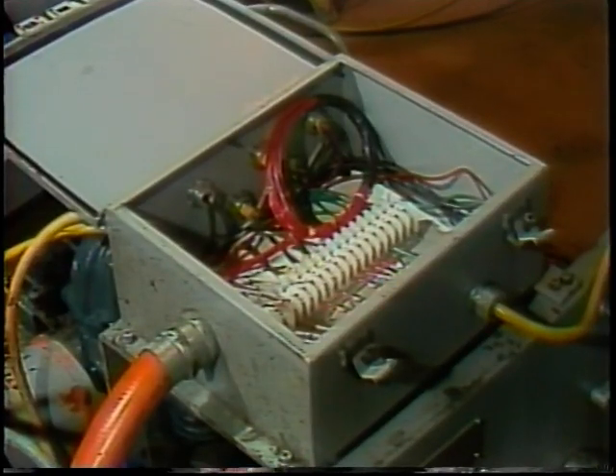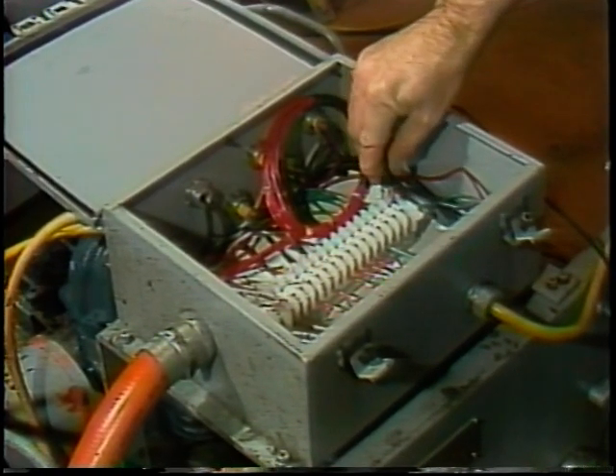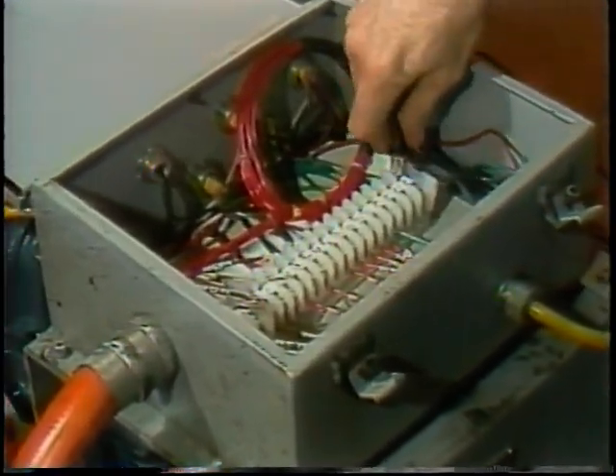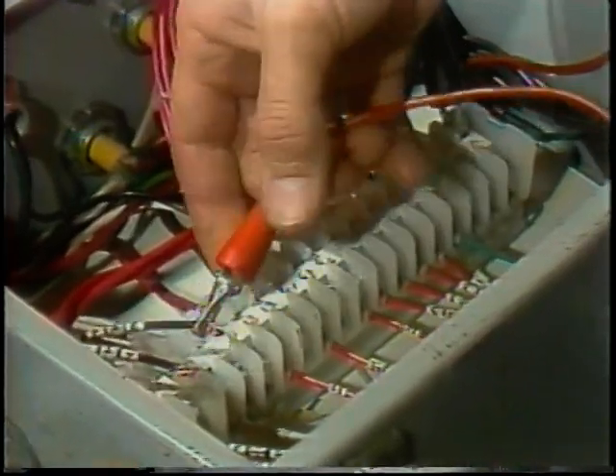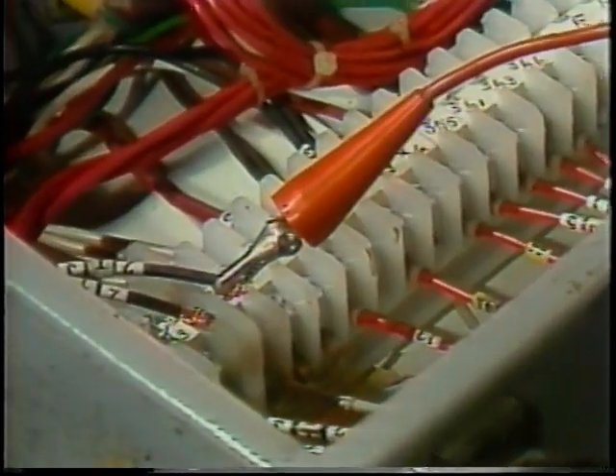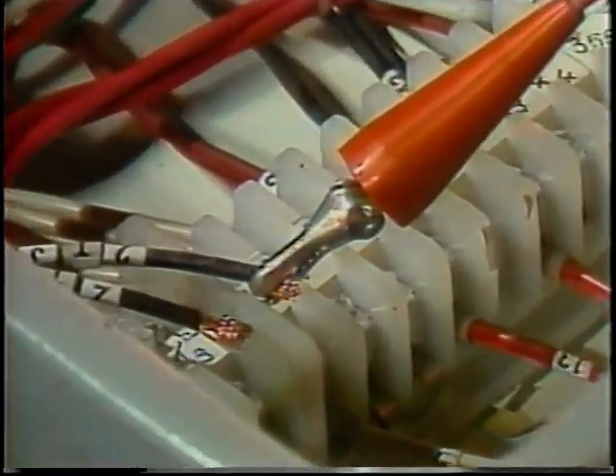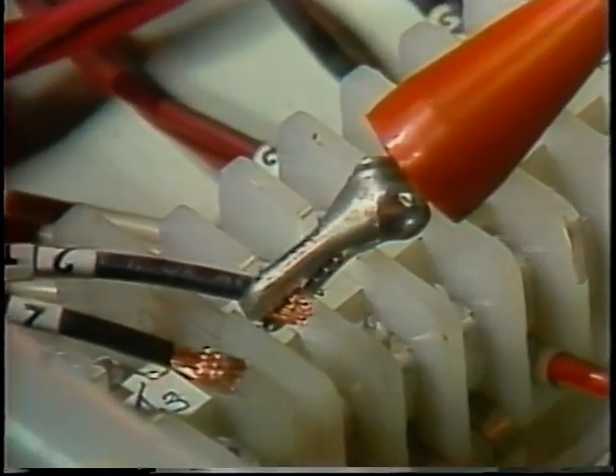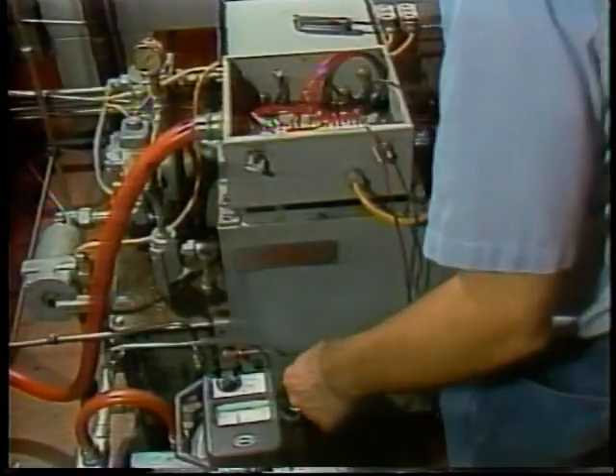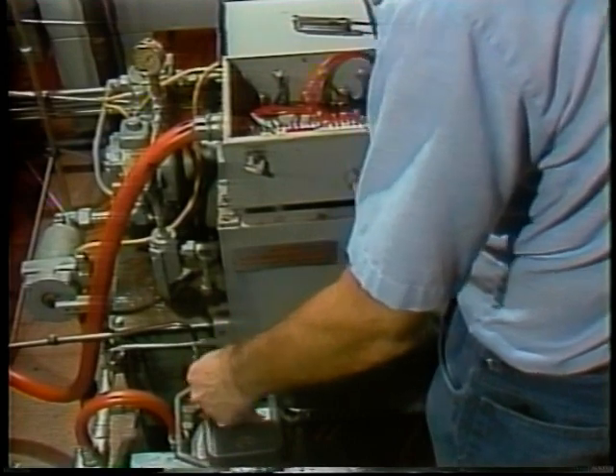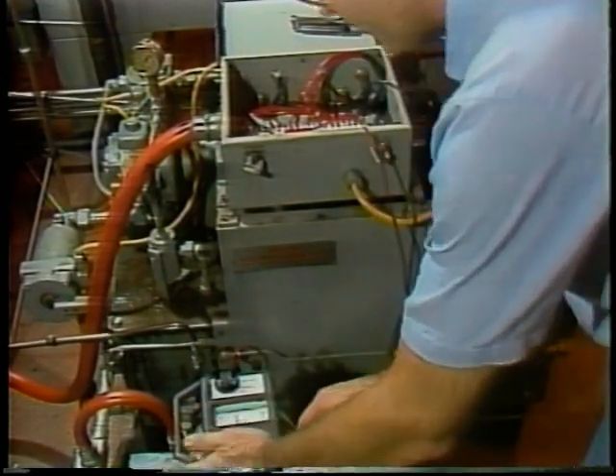Using a megohmmeter is different from taking a reading with a standard ohmmeter. For one thing, remember the voltage involved. Do not touch the lead clips or probes while applying megohmmeter test voltage, and make sure the voltage will not be applied to any solid-state equipment connected to the motor lines. If there is any question, disconnect the motor lines before applying the megohmmeter test voltage.